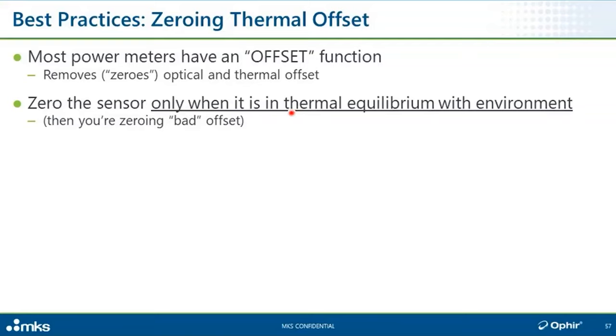Basically, what we always recommend is wait until your sensor is in thermal equilibrium with its environment before you start working with it. And that way, when you then have an offset, it's an offset caused by some heat source near the area, or a light source near the area of the measurement. And that's an honest, bad offset that's constant. And then that's an offset that you'll be correctly subtracting when you press the offset button.